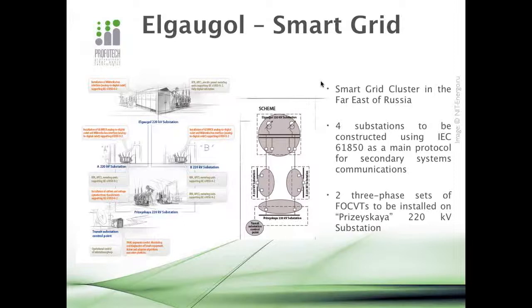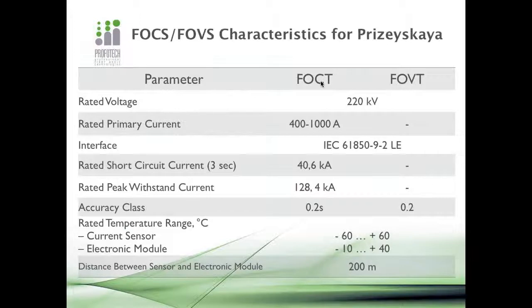You can see in the middle of the slide there's a picture, and it shows that there are 4 substations to be installed, and one of them is Prizeyskaya 220 kV substation, and 2 3-phase sets of fiber optic current transformers will be used there. But what is special about this project is that all substations would adopt the IEC 61850 protocol as the main protocol for secondary system communications. So the characteristics for Prizeyskaya substation are shown on the slide.